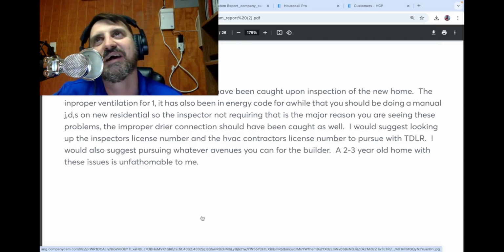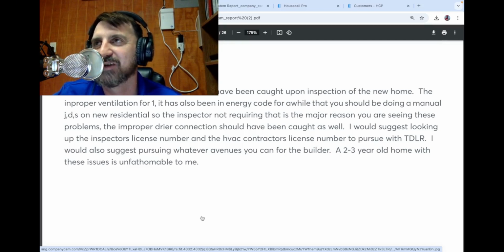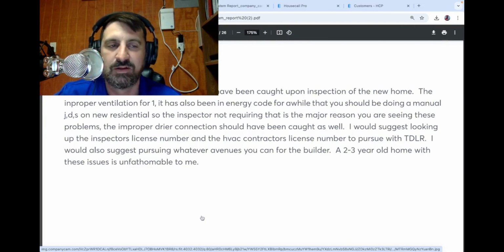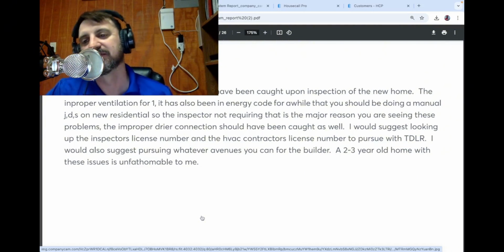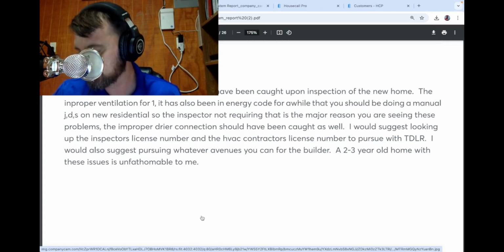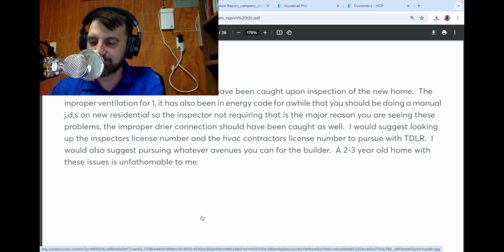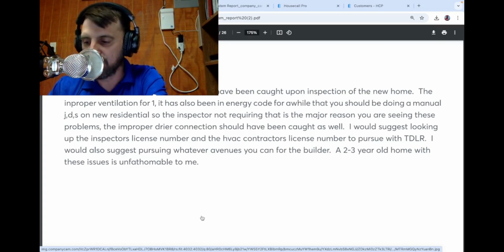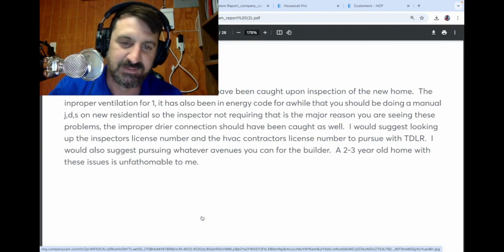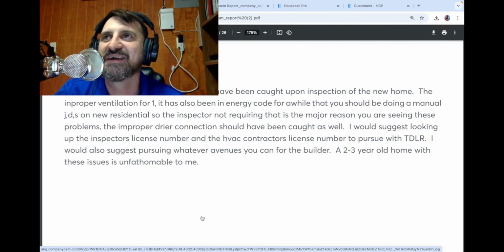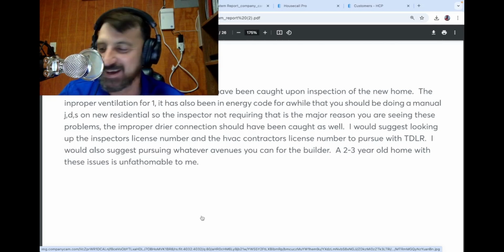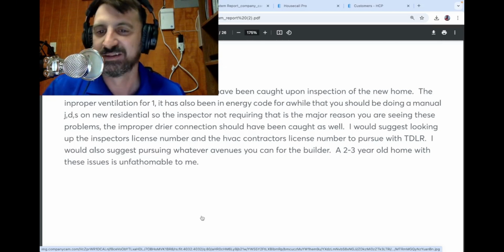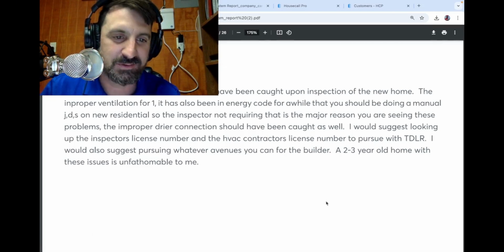I mean, if you say, okay, he didn't catch that there's no control on the ventilation, he just saw the ventilation duct. Okay, bad day for an inspector. Don't do the manual J because you don't think the energy code applies. Okay, terrible oversight, but understandable. Missing a P-trap right in your dryer duct, right in front of your attic access. I don't know how that gets missed. So anyways, I put that in there.